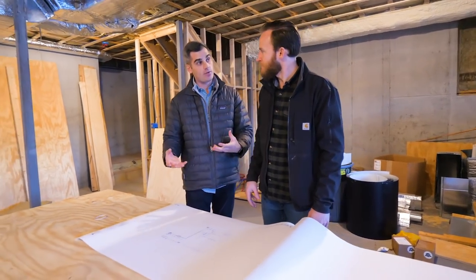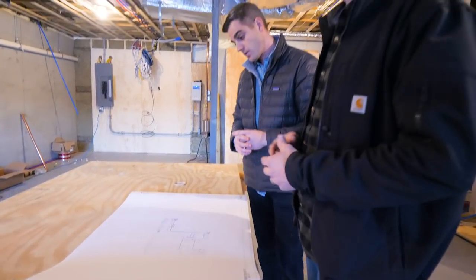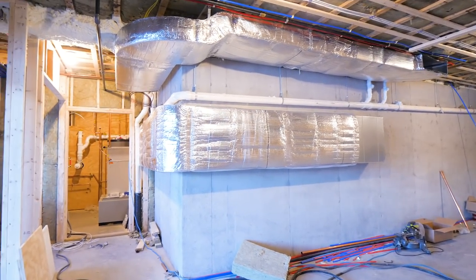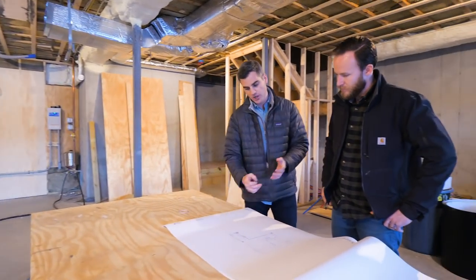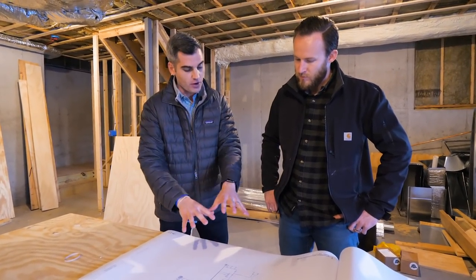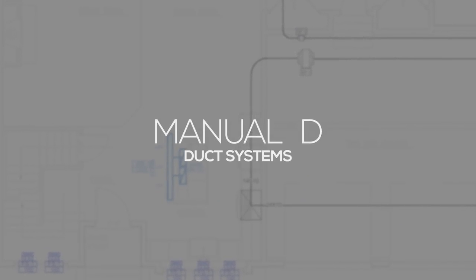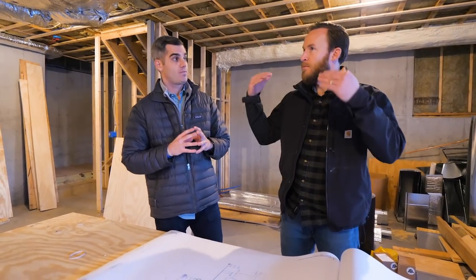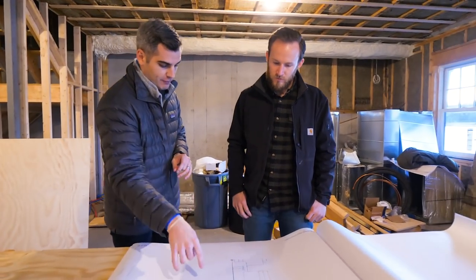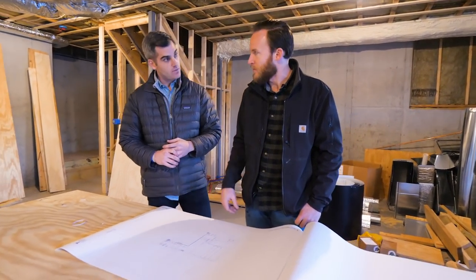This is the actual layout of the equipment and the ductwork — first floor but viewed from the basement. If you look up you can see the ductwork ran across the ceilings; we've got our mechanical room in that back corner. We laid everything out to scale — we know exactly where the boiler is going, where the water is going, where the air handler is going, where the dehumidifier is going. The ductwork has also been sized using Manual D, so every bit of ductwork is sized appropriately — we're minimizing size and only building what we need, sized exactly for the room it's serving.